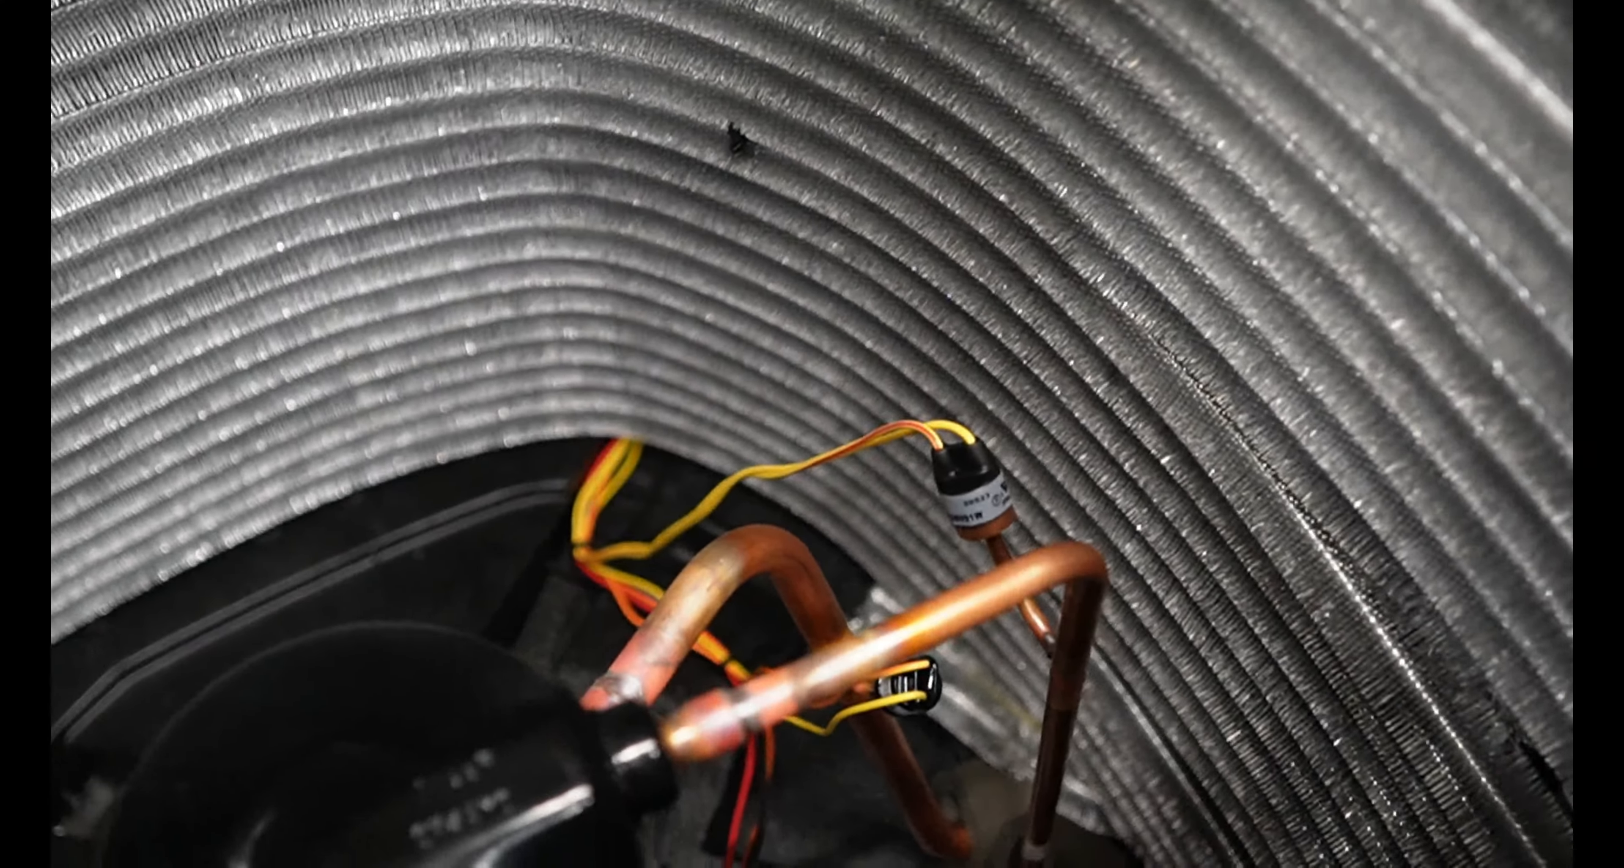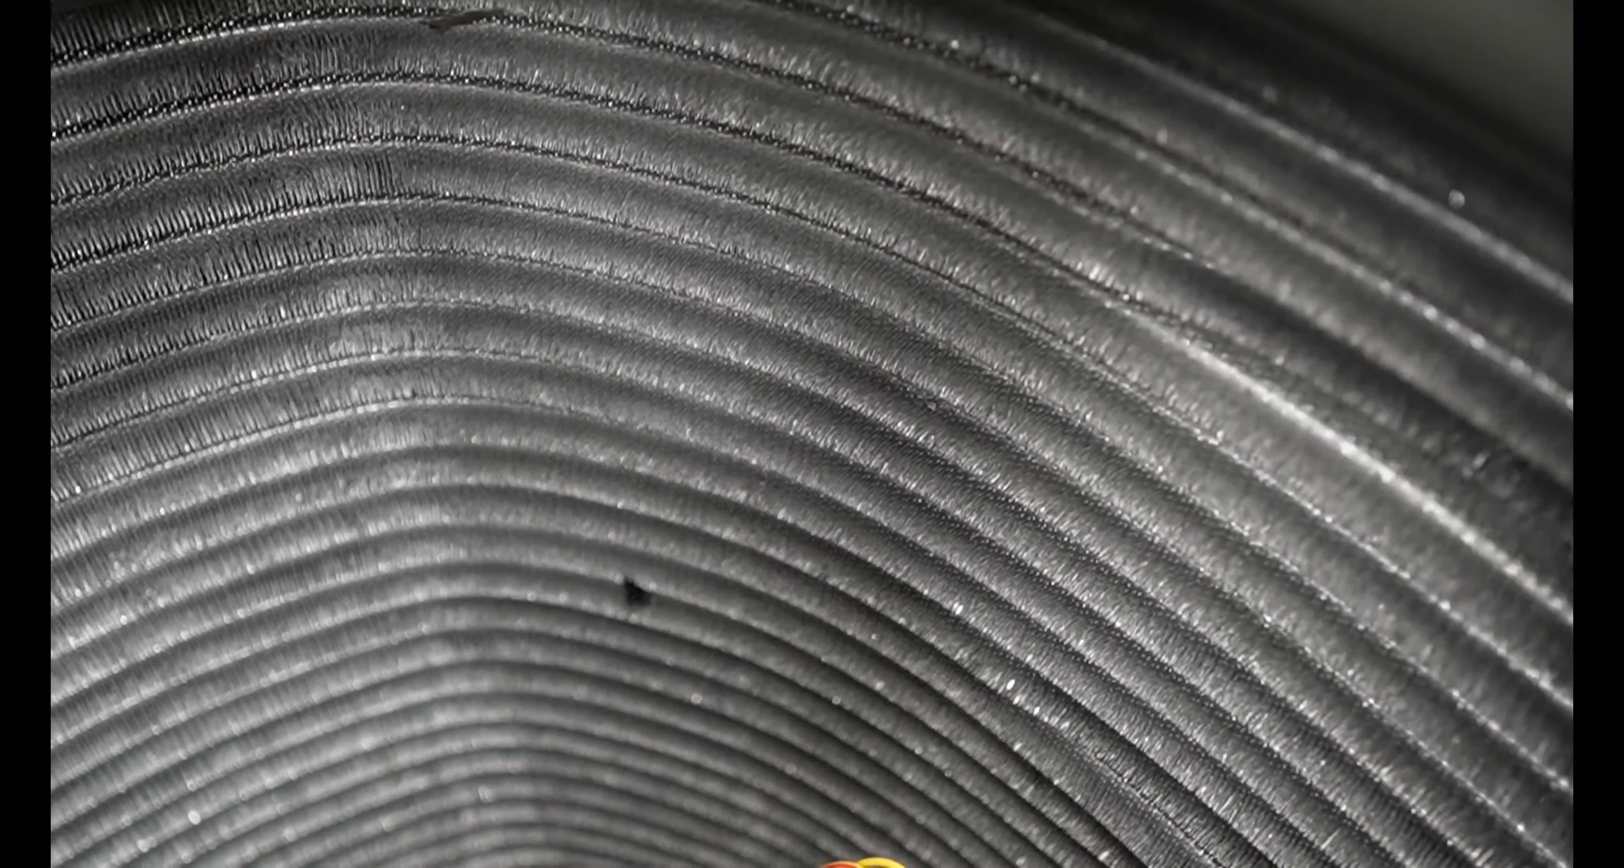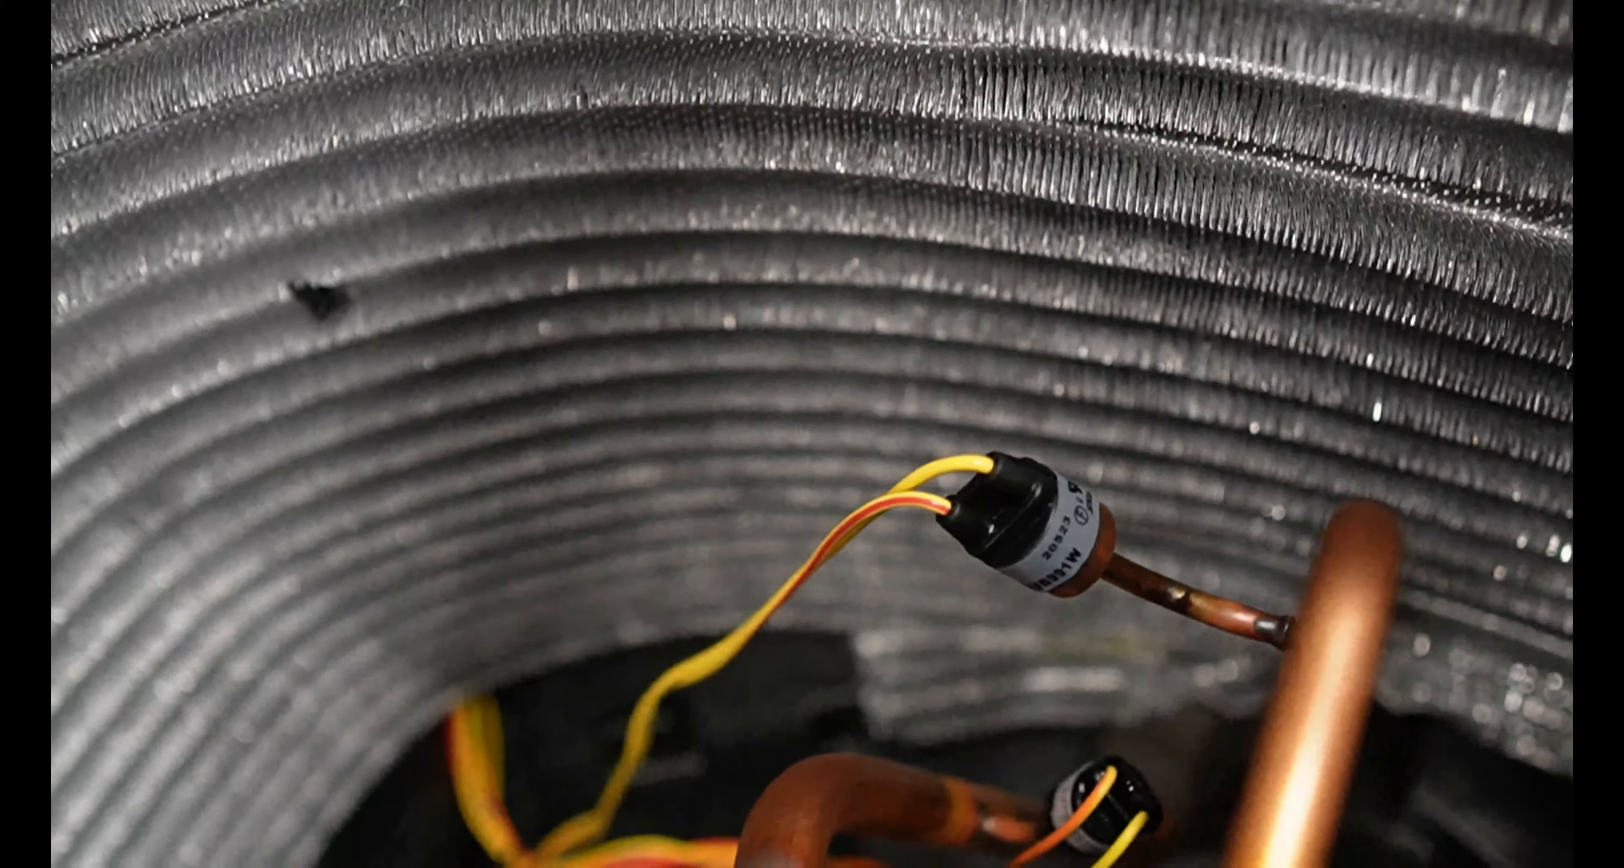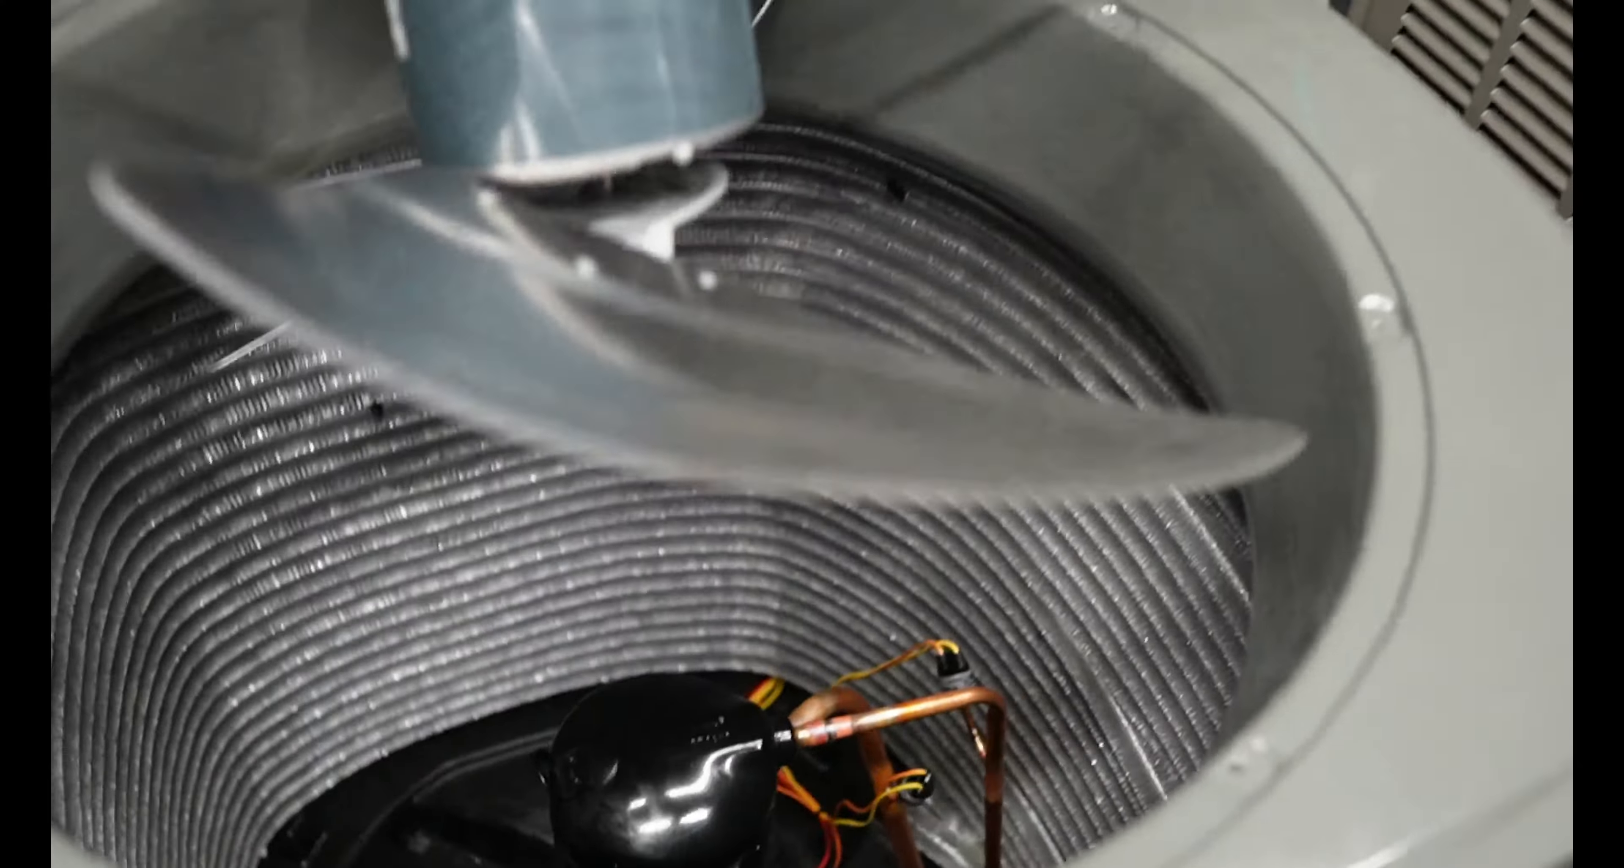So they got a high and low pressure cutoff switch. Very good feature. We have these aluminum spine fin coils. There's 3/8 size tubing in there. And look on the bottom, you see that row and there's nothing connecting to it. So they don't rub on the bottom there, you don't leak refrigerant. Pretty good feature there. And it's got the plastic bottom, which never, ever rusts out. Perfect.